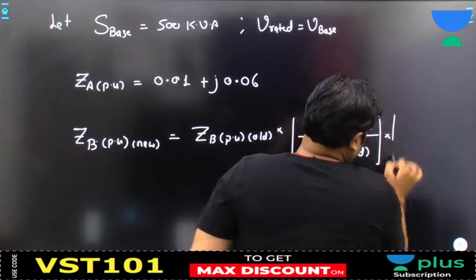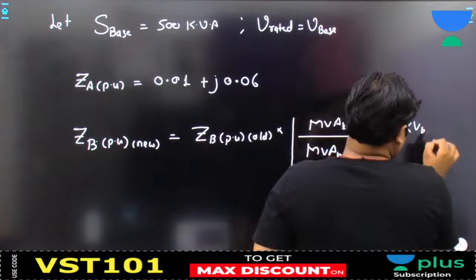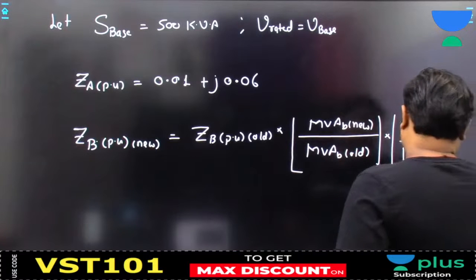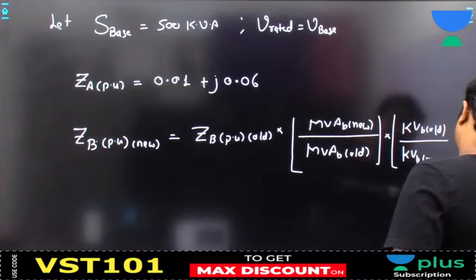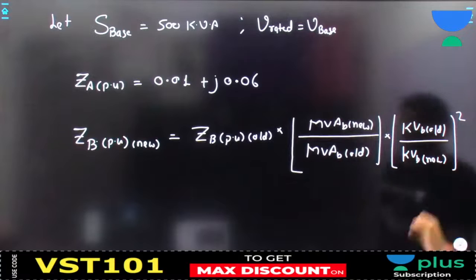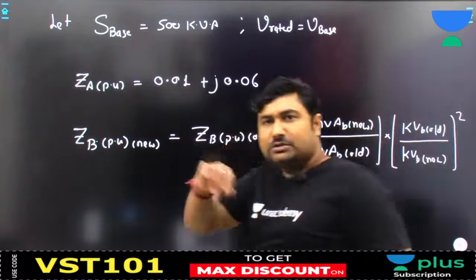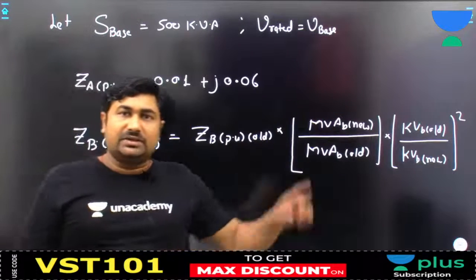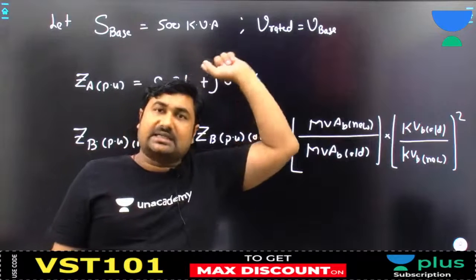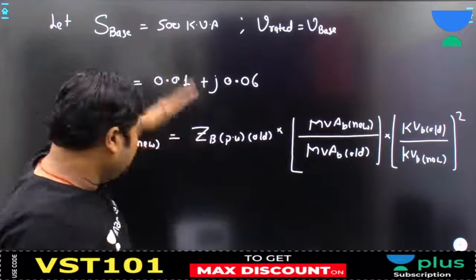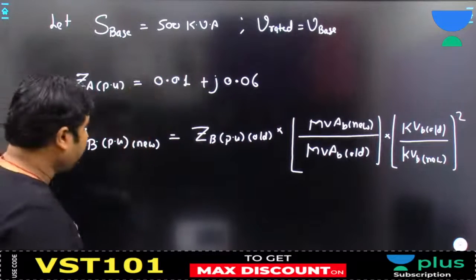into KV base old by KV base new squared. Now, the old value is the rated values of transformer B and the new value is the value which we have selected as a base value for finding the common base for both. Is it okay? Yes sir.